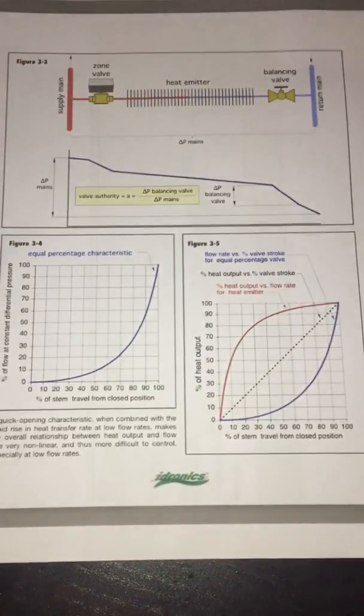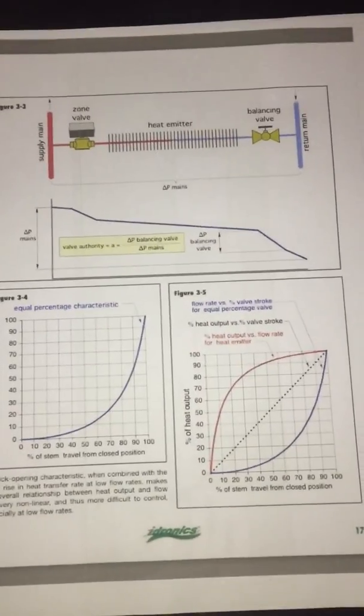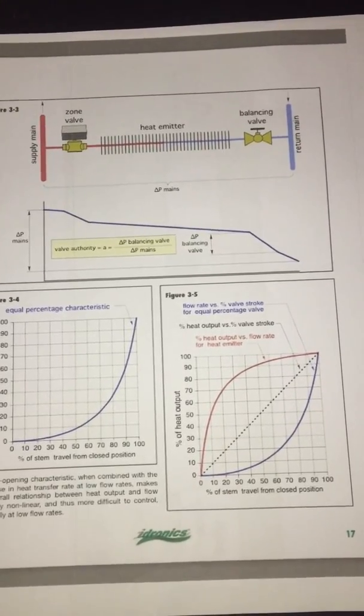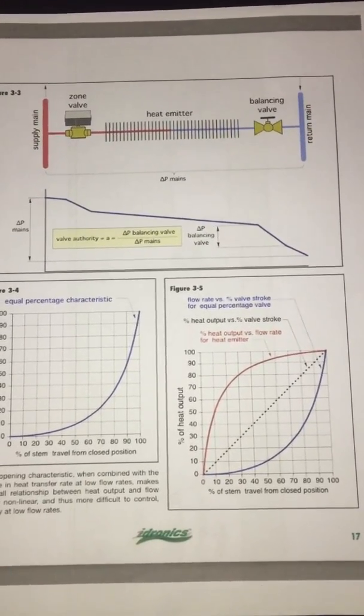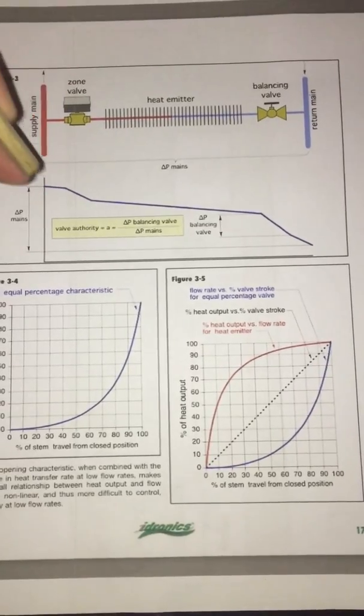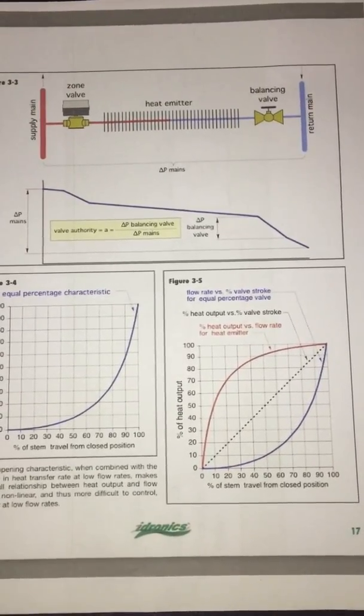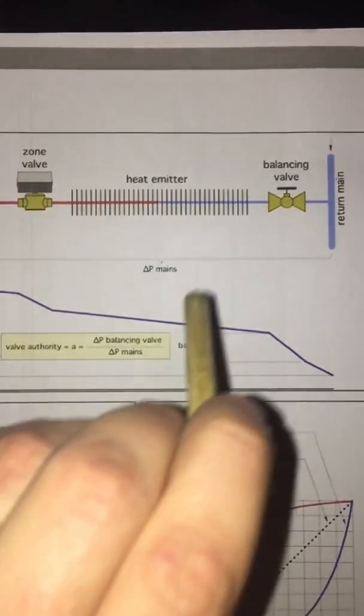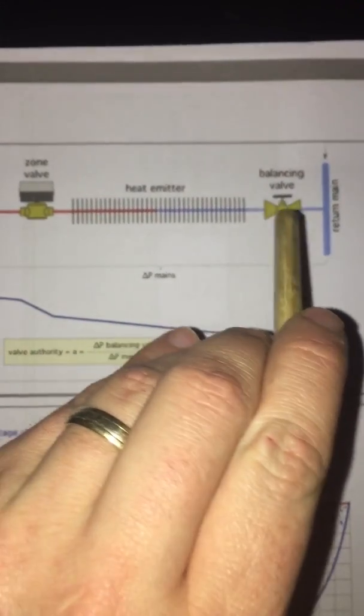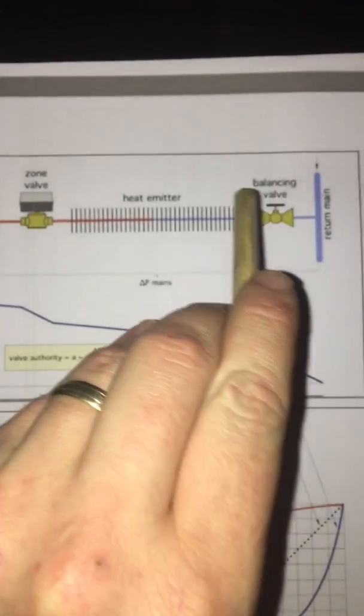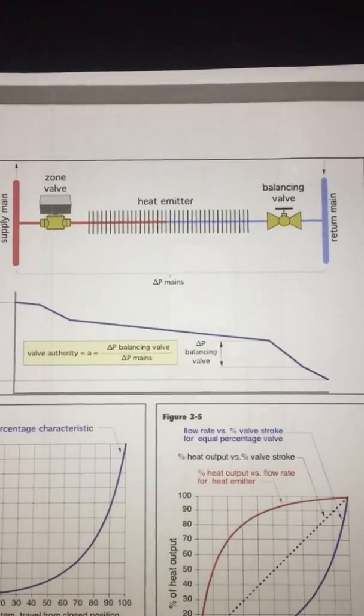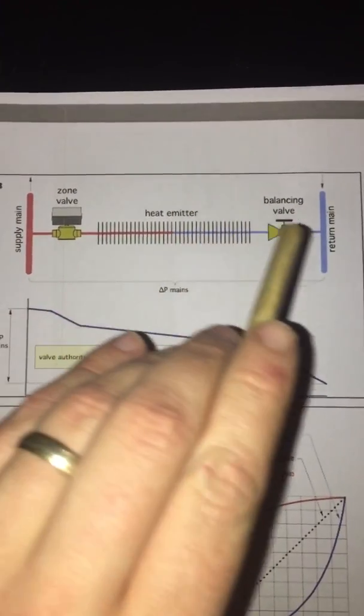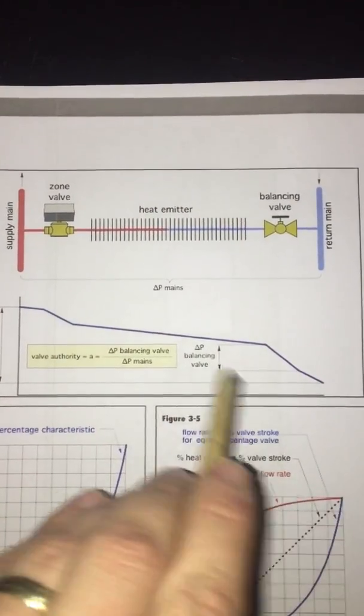So let's start with valve authority. When we're selecting a balancing valve or any valve that controls flow through a circuit, may also be a three-way rotary mixing valve, then we want it to have good authority which will mean good flow control. How we do that is we need a balancing valve which has a delta P differential pressure, pressure drop across the valve of around 20 to 50% of the total circuit it is controlling, including the valve.